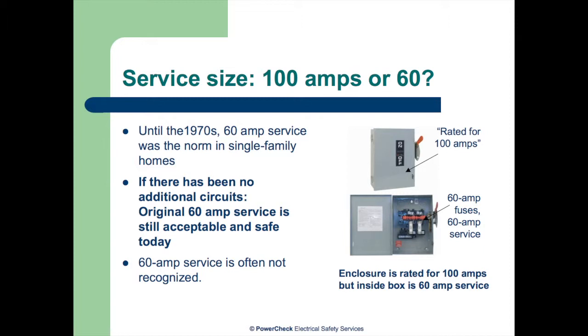It's not because the 60 amp was unsafe, it was because of the potential of a future upgrade. You needed extra power, and at the time of installation, it was only 5% more in the cost of your installation to put in a 100 amp versus a 60 amp. It doesn't mean the 60 amp is not safe. It means that it needs to be visited case by case.